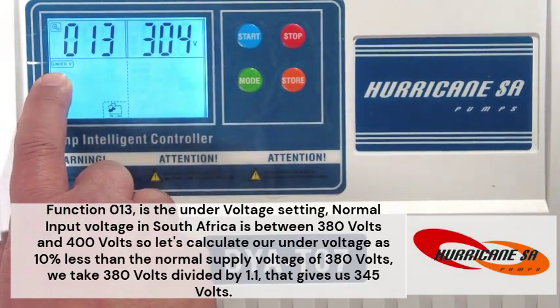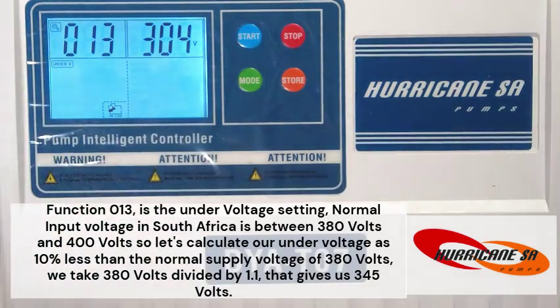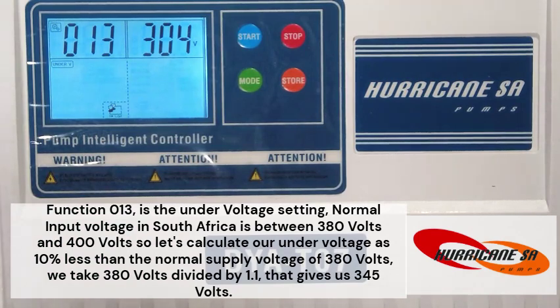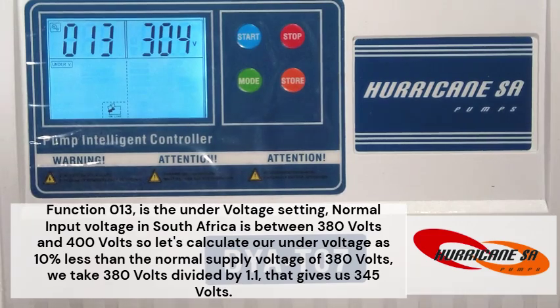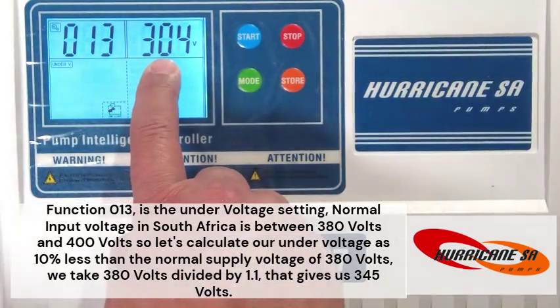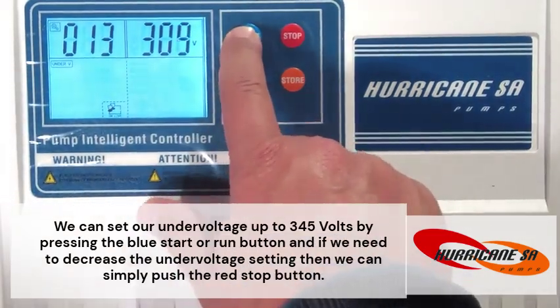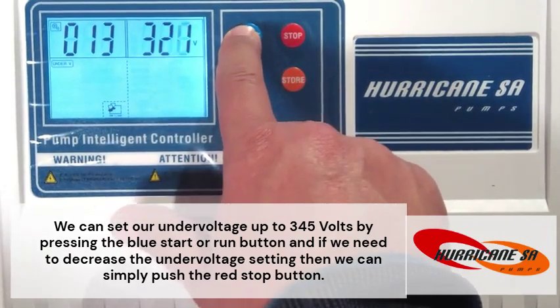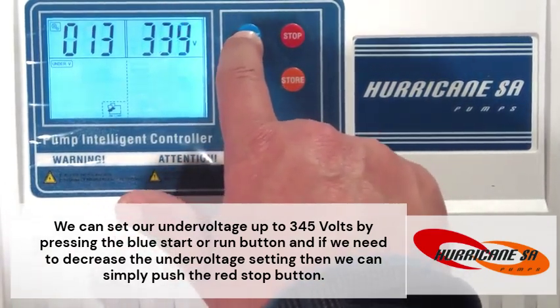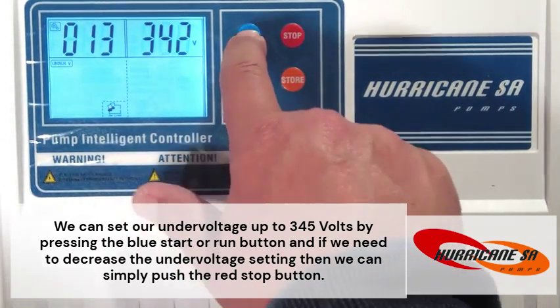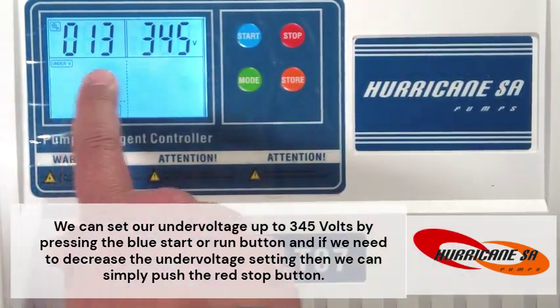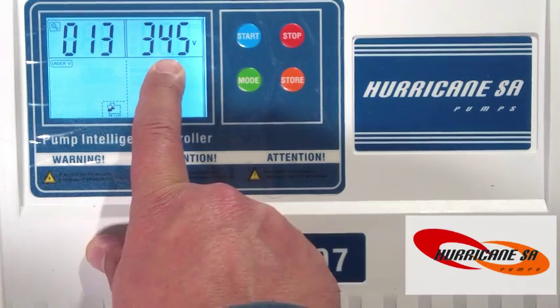Function 013 is the under voltage setting. Normal input voltage in South Africa is between 380 volts and 400 volts. So let's calculate our under voltage as 10% less than the normal supply voltage of 380 volts. We take 380 volts divided by 1.1. That gives us 345 volts. We can set our under voltage up to 345 volts by pressing the blue start or run button. And if we need to decrease the under voltage setting, then we can simply push the red stop button.